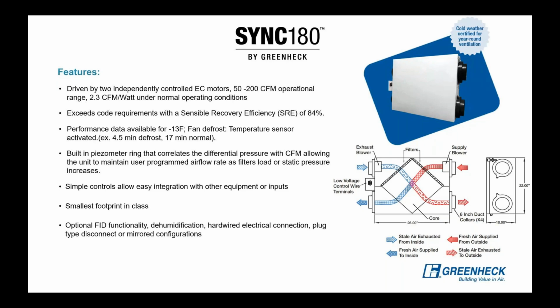It has a built-in piezo ring, which will help you automatically balance them in the field. Has really simple controls. It has some other nice functionality like a FID, which you don't really need in our state yet. It is required by California by Title 24, which is a fault indicator display. But for now, just know that we can do it. It also offers a mirrored configuration if you need it, and that unit has a pretty small footprint of 22 inches wide by 26 inches long by 10 inches deep. So it'll fit in most applications, especially where you have a 24-inch on center joist.